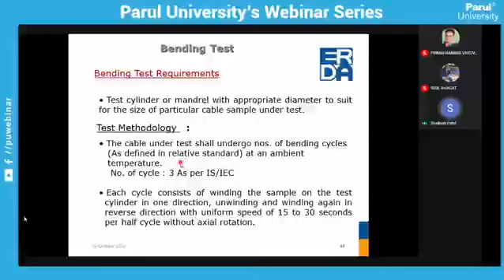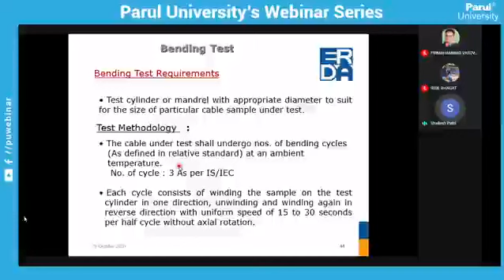Because it is basically a simulation, considering the laying of the cables, cable will undergo different kinds of bending, and because of that bending, cable constructions like copper screen, conductor, semiconducting layer, armor may get damaged. Immediately we carry out the partial discharge measurement. There should not be any detectable discharges after bending test. So that is the conformity for the bending test.